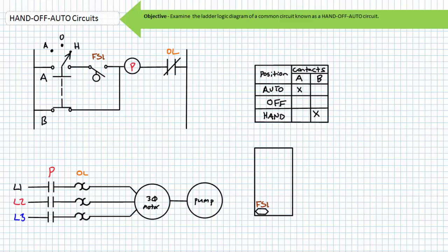Similarly, the hand setting overrides the automatic nature of the system. In hand mode, the selector switch provides an alternate path that directly energizes the P contactor coil, circumventing the automatic logic.